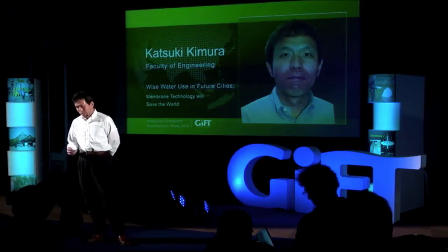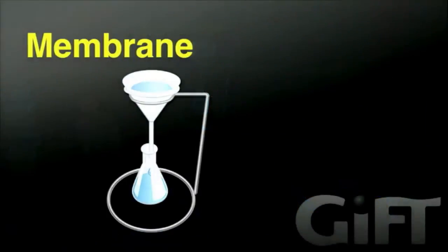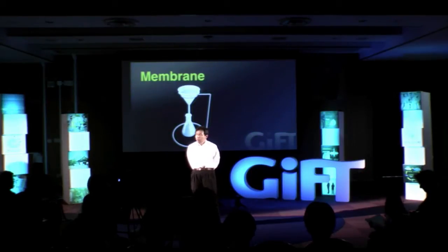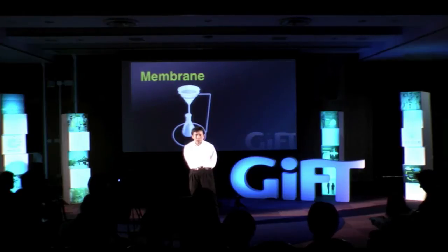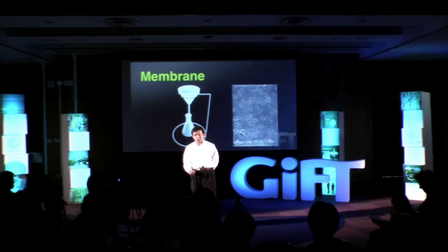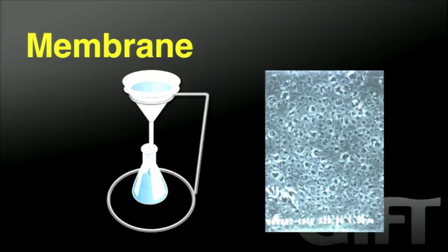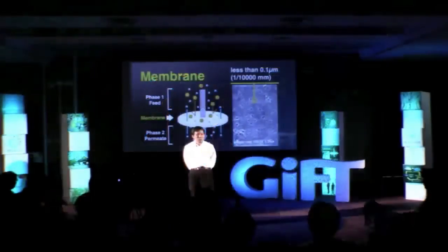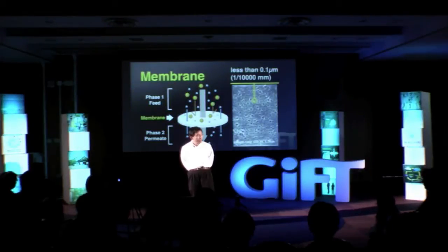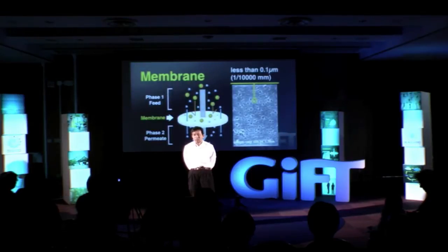First of all, I'd like to briefly explain what the membrane is like. The membrane that we use for water treatment or wastewater treatment is very similar to filter paper you used to use in experiments in junior high school or elementary school, but much tighter and much stronger. When we look at the surface of a membrane with large magnification, you see numerous tiny pores. The principle of membrane separation is very simple: when you apply a driving force such as pressure difference across membranes, small constituents smaller than the tiny pores will penetrate to the permeate side, whereas large constituents bigger than the micropores will be retained.